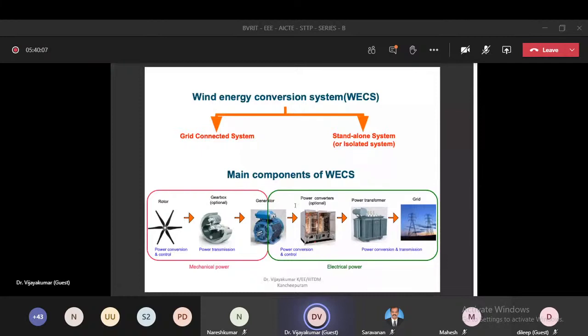So both the gearbox and power converters are optional. I'm using a power transformer between the wind turbine and the grid. Its purpose is to match up the voltage—if my incoming voltage is 110 volts and the grid voltage is 220, I need to match it. Another important application is providing electrical isolation, so that any fault in the grid won't transmit to the wind turbine, and any fault in the wind turbine won't transmit to the network, helping avoid blackouts.